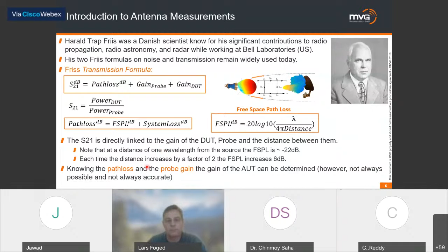The simple way to measure antenna gain, which is to use what we call the gain substitution technique, is to first make a calibration of the system in which we use a reference antenna that has a known gain. By recording the S21 between the probe and the reference antenna, we can then do a second measurement, which will be the one in which we'll include the unknown antenna. In this case, it's a mobile device, but it could easily be a satellite. It's exactly the same procedure. And from these two measurements, we can then determine what is the gain of the unknown device here, simply from the measured S21 in this case, and then a correction term that is a calibration factor that comes out of this calibration we have done on the system using a reference antenna.